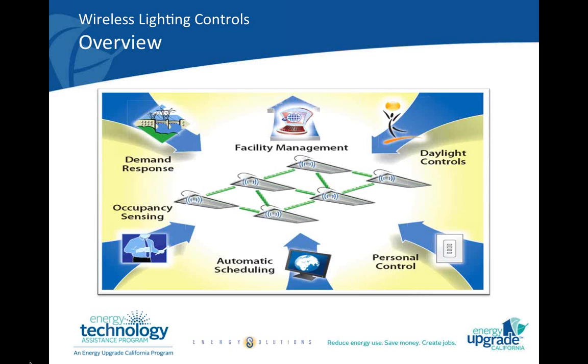And that allows you to see real-time performance of the system on a fixture-by-fixture level, letting you know what fixtures are on, what fixtures are off. And from there, you can reprogram and re-optimize your system continuously, controlling which fixtures respond to which inputs. So you can have X number of fixtures that respond to Y occupancy sensor, and you can have one fixture that is specifically programmed for the needs of one person. And all of these different programs can layer on top of each other with different priority levels, allowing you to really have the most optimized control and optimized savings that you can get from the system. Next slide, please.